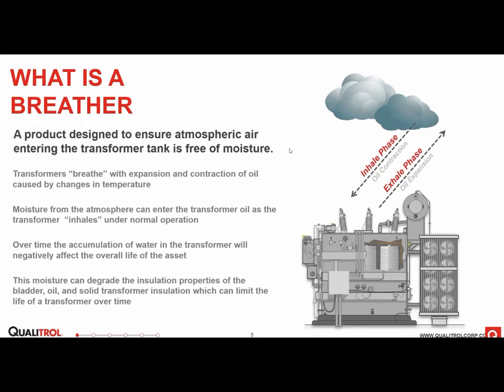So what does a breather do? A breather is designed to ensure that moist atmospheric air does not enter your transformer. So with expansion and contraction of the transformer oil on a conservator style transformer, the transformer inhales or exhales air from the inside to maintain a constant pressure with the changing oil levels in the conservator.